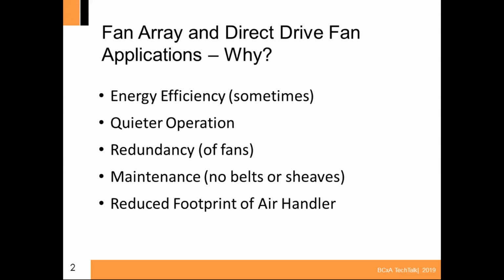We talk about the types of fan arrays, and I'll show an exact example from the National Institute of Health that we applied for redundancy. Maintenance is another big issue, and not just the maintenance with no belts and sheaves. You also reduce the drive losses, so the efficiency increases in that aspect, because you don't have a belt and sheaves and that drive loss and friction. You're using just the motor and the fan.